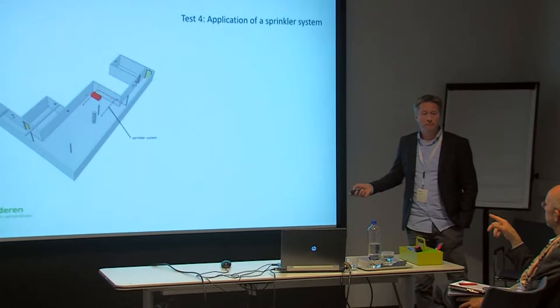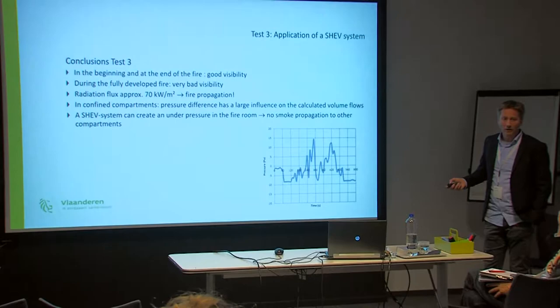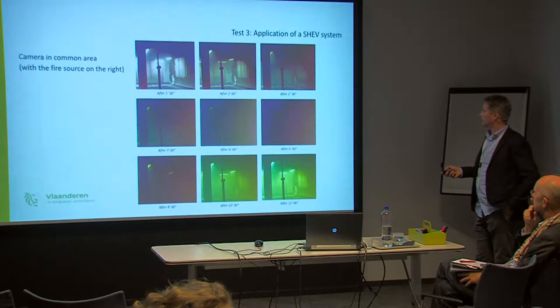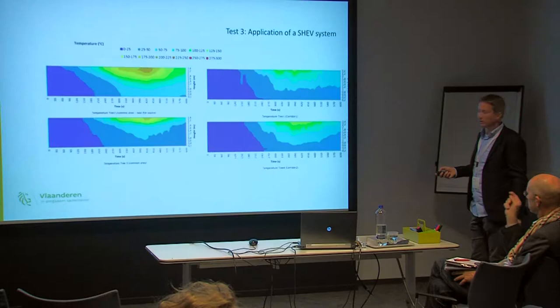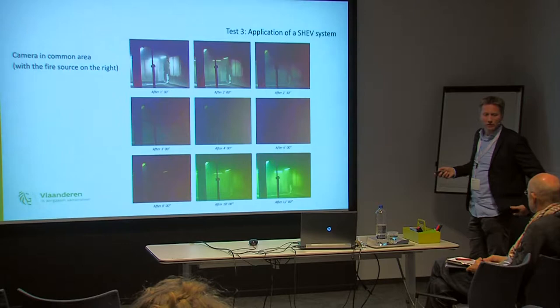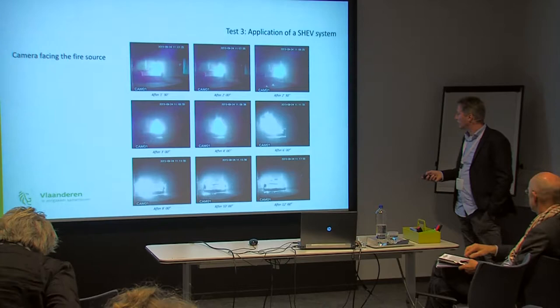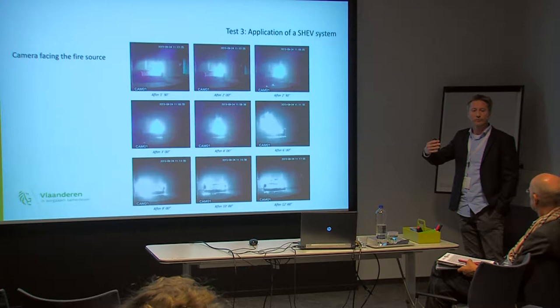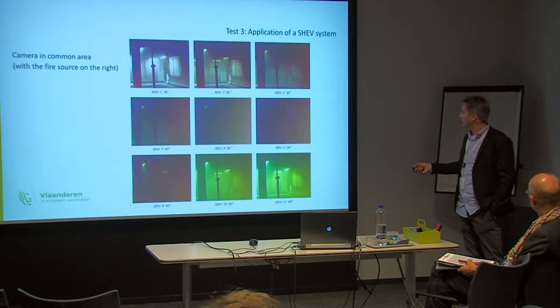Are there any questions concerning the third test? Did I see that the fire was finished 10 minutes after ignition and another picture at 12 minutes? It was 12 minutes, yes. I was confused, at a certain moment I was expecting it to be finished. But you see, the couch is still burning at 12. Yeah, like I said, it gives maybe a bad impression. This is not fire flames that high. No, because if these flames were the same as these, you would not have the visibility after 12 minutes there. You would have the same as this one.